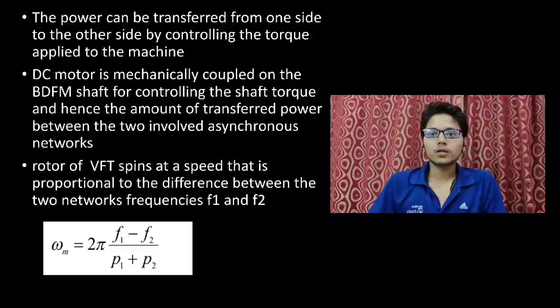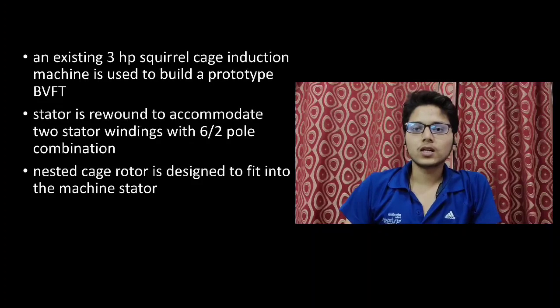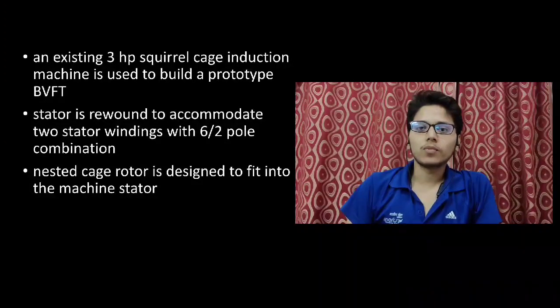The rotor of the VFT spins at a speed proportional to the difference between the two network frequencies F1 and F2, given by the equation. The stator frame of an existing 3 horsepower squirrel cage induction machine is used to build a prototype BVFT. The stator is rewound to accommodate two stator windings with a 6 by 2 pole combination. The number of turns per phase for both windings and their cross-sectional areas are selected to ensure the same acceptable air gap flux and power.